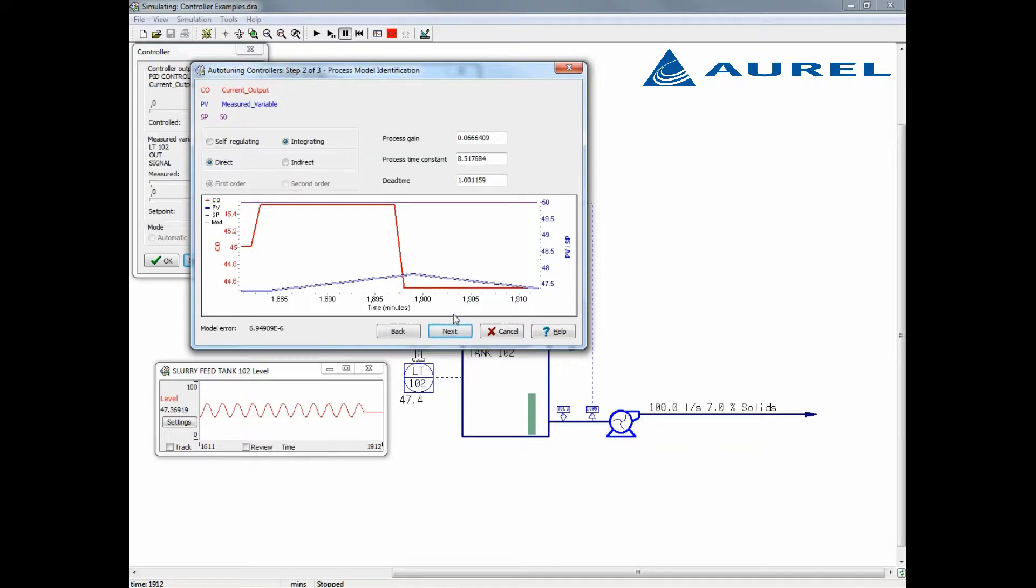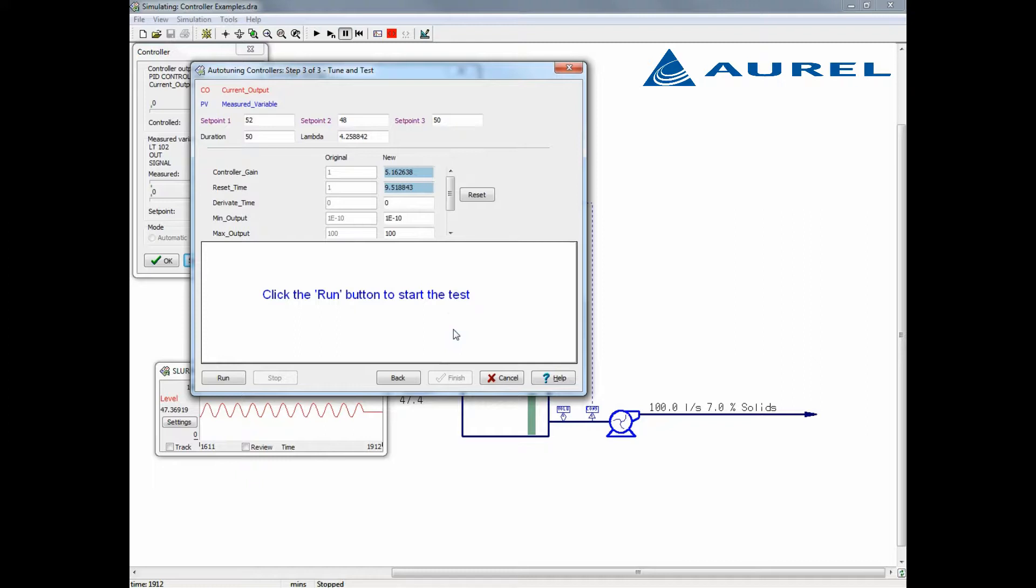Now we will continue to the next step of our bump test. On the second step, we can see the controller model that Aurel is suggesting. We're using an integrating controller which is expected for tank level. We also see the process gain, time constant, and any observed dead time for this controller. If we're satisfied with these parameters, we move on to the final step, which is final tuning and testing.